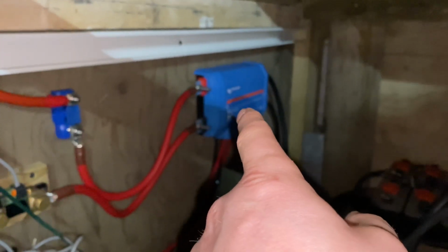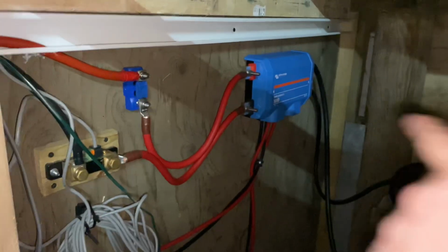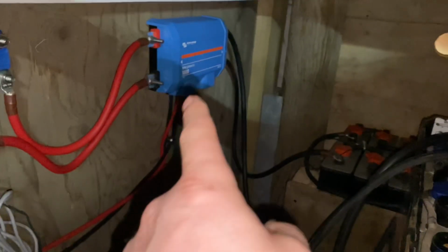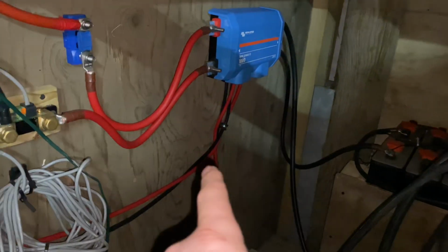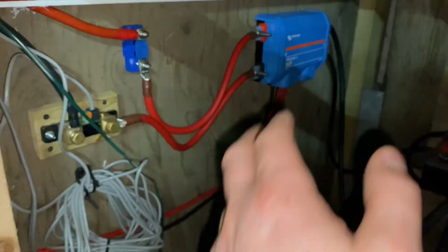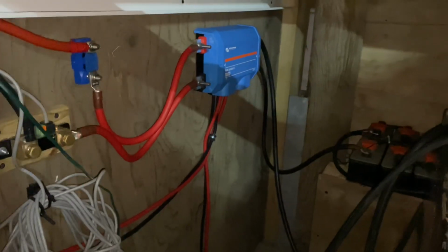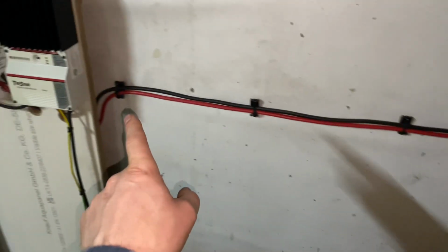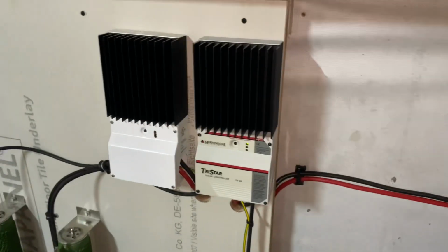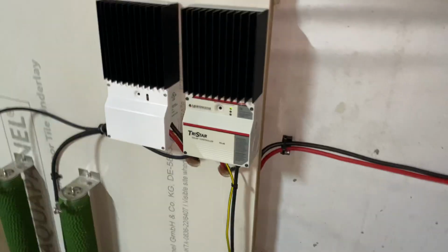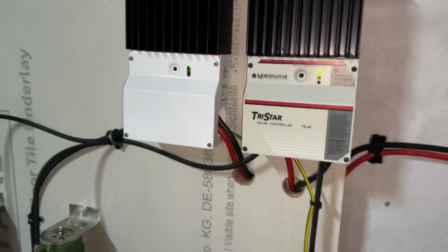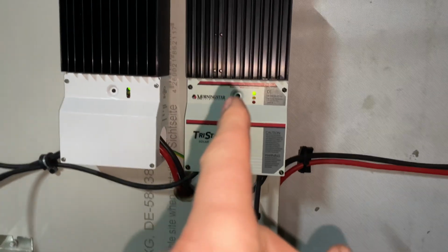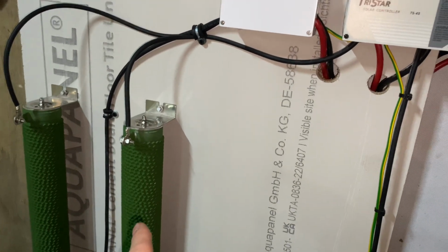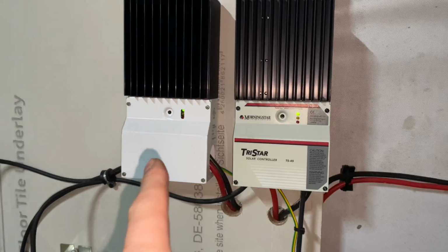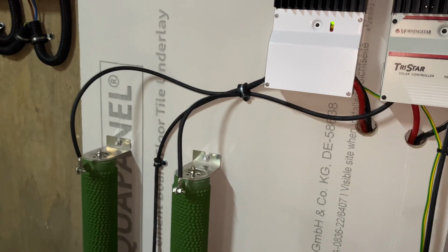We've then got another bus bar. Past the fuses between the batteries and the fuse, I've got a bus bar, and that is for dump loads. So if the fuse blows, we can still continue to dump. If something catastrophic happens, we can still dump. So we've got 2 lots of 16mm cables going to TriStar. These are TriStar PWM charge controllers, and we've set these up in diversion mode. So when this one hits 59.5 volts, it dumps 2 kilowatts into that wire wound resistor. When this one hits 60 volts, it dumps 2 kilowatts into a wire wound resistor.